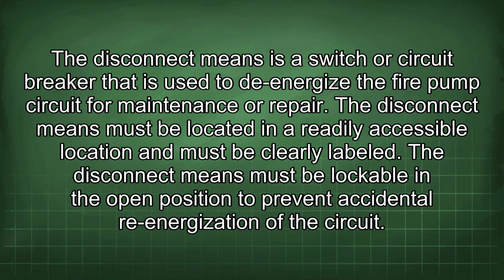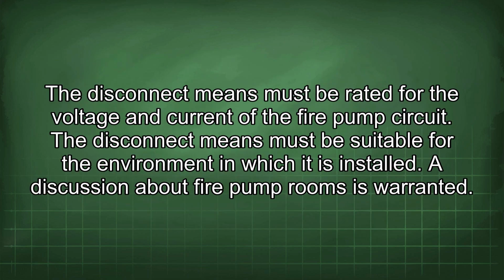The disconnect means must be lockable in the open position to prevent accidental re-energization of the circuit. The disconnect means must be rated for the voltage and current of the fire pump circuit. The disconnect means must be suitable for the environment in which it is installed. A discussion about fire pump rooms is warranted.